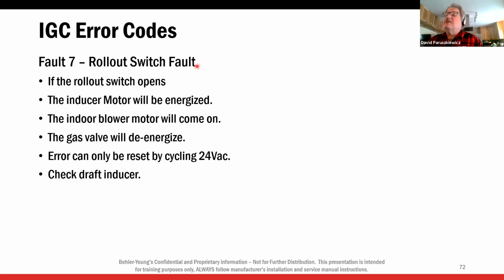Okay, fault code 7, rollout switch. If the rollout switch opens, the inducer motor will be energized, the blower motor will come on, and the gas valve will de-energize. It can only be reset by recycling 24 volts, so I have to kill power to the unit to recycle. Check the draft inducer. For a rollout switch, there are a couple of things. Like I just said, the draft inducer is plugged. Somebody put the wrong size wheel on there. That happens. That wheel blew apart, and it's a Hall effect sensor, so it still keeps running. Cracked heat exchangers. Prevailing wind: sometimes the unit's situated in a way that the prevailing wind is actually blowing the burners back out of the heat exchangers. And again, check the draft inducer.